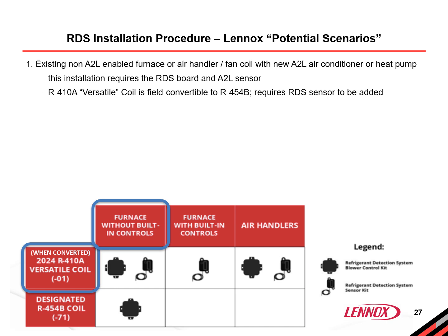Here's a common upgrade scenario: adding a new A2L air conditioner or heat pump to an older furnace or air handler that is not A2L enabled. In this case, we'll need to install both the RDS board and the A2L sensor. These components ensure the system can detect and respond to any potential refrigerant leaks, providing safety for the homeowner and protecting the equipment. A key takeaway here is the Lennox Versatile Coil.